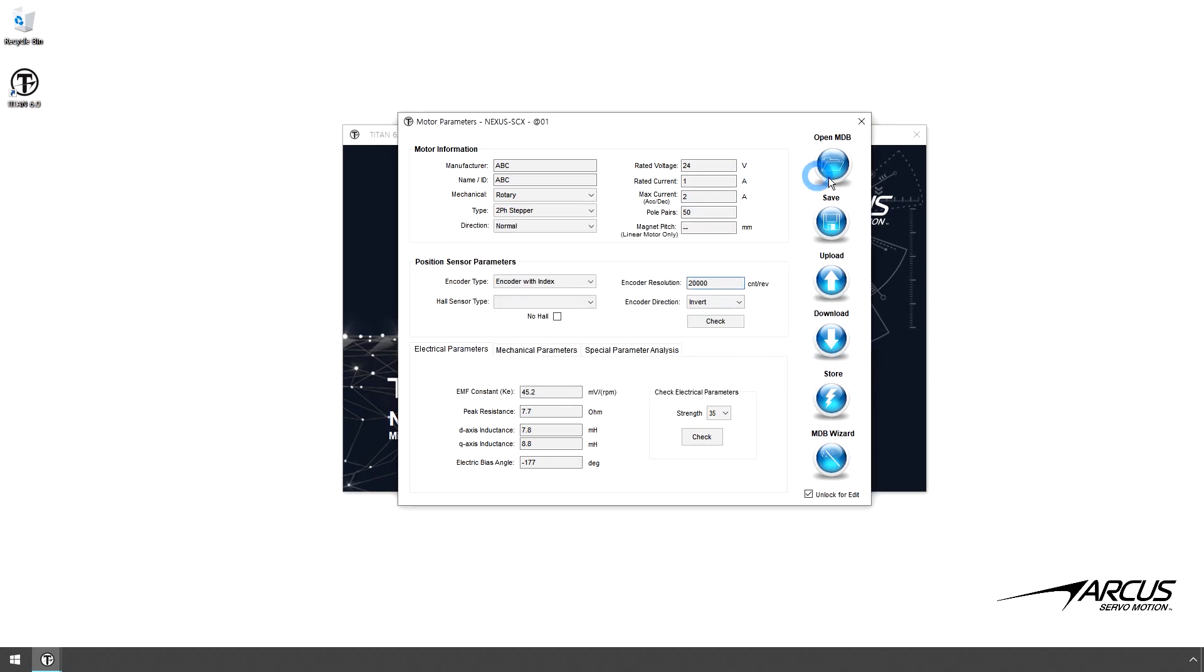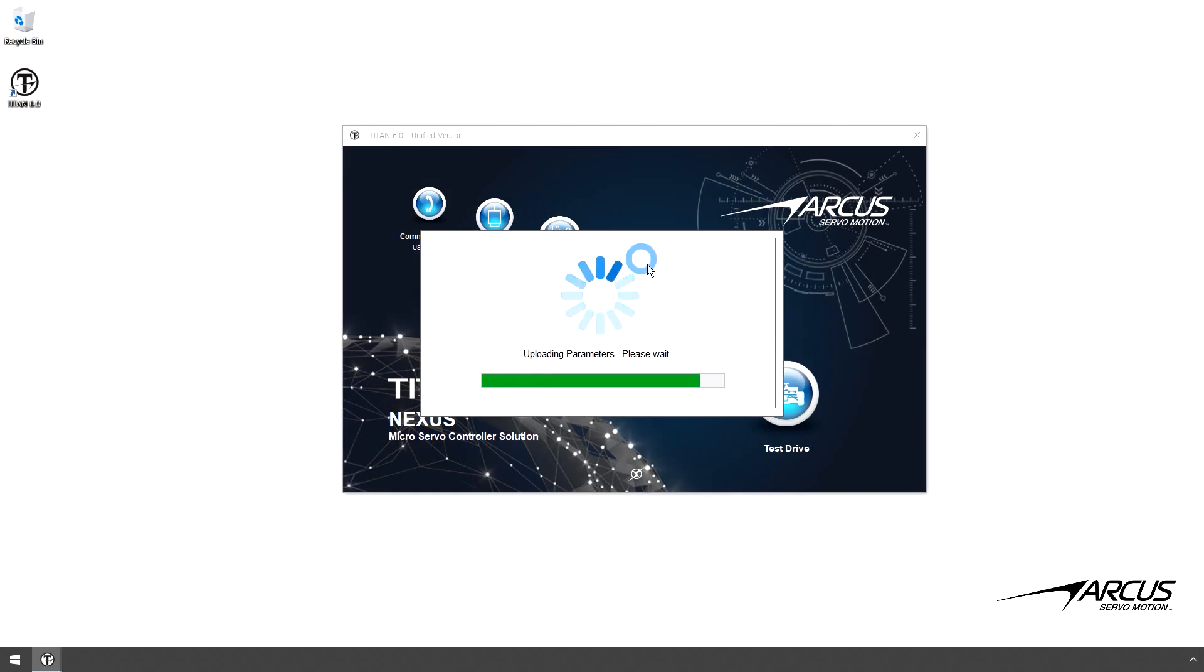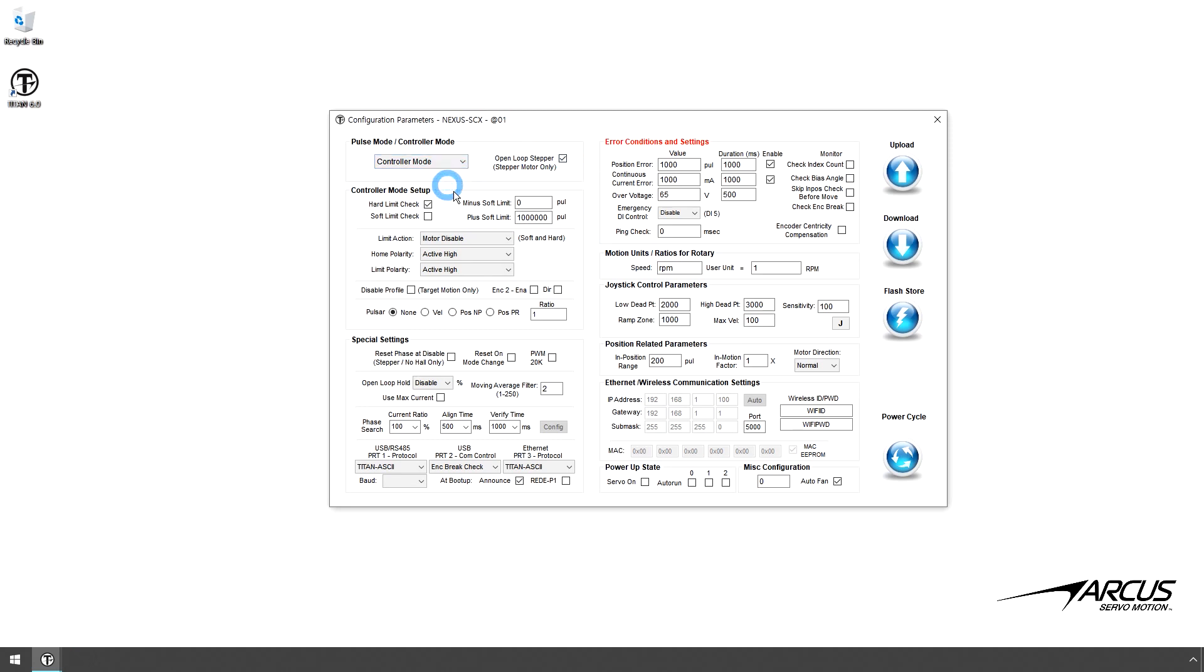Now go to the Configuration window. Check the open-loop stepper control and select the controller mode. If you are using the Titan as an open-loop driver, select the pulse mode. In this example, we will use the controller mode.